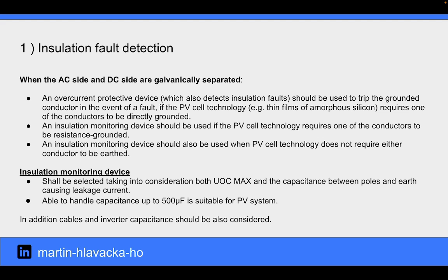When the AC side and DC side are galvanically separated, an overcurrent protective device should be used to trip the grounded conductor in the event of a fault if the PV cell technology requires one of the conductors to be directly grounded. An insulation monitoring device should be used if the PV cell technology requires one of the conductors to be resistance grounded. An insulation monitoring device should also be used when PV cell technology does not require either conductor to be earthed.